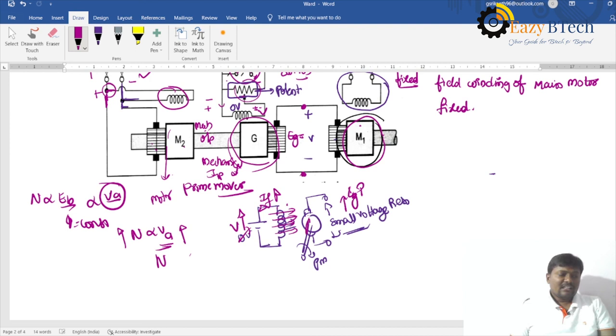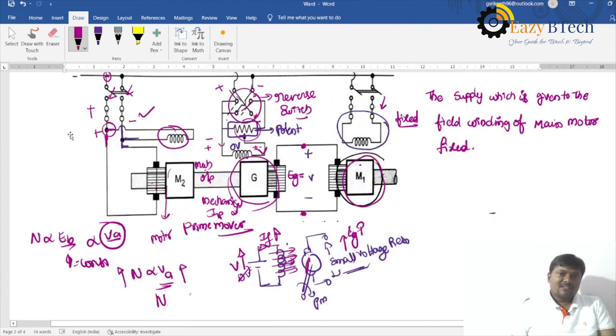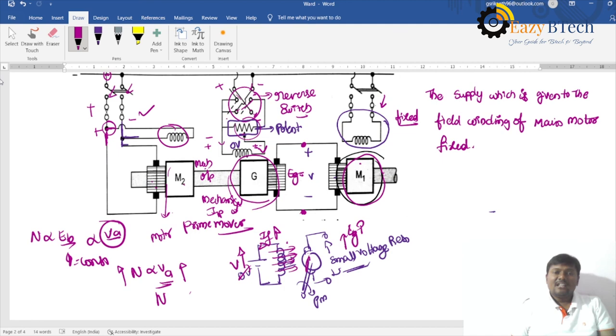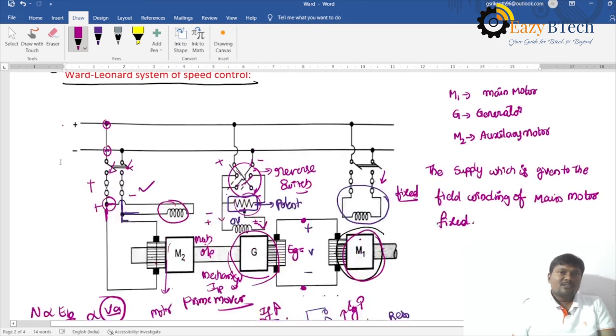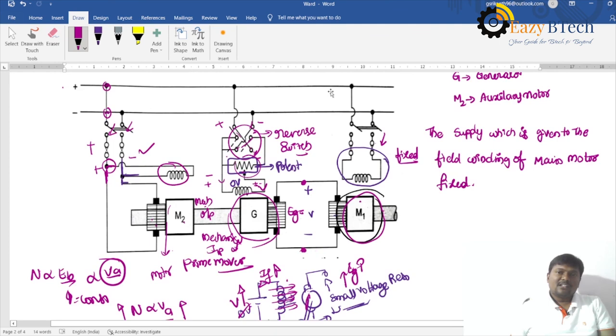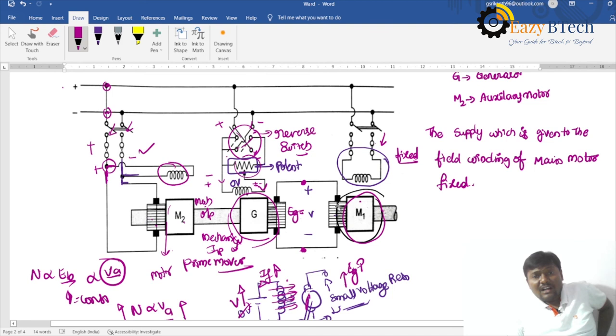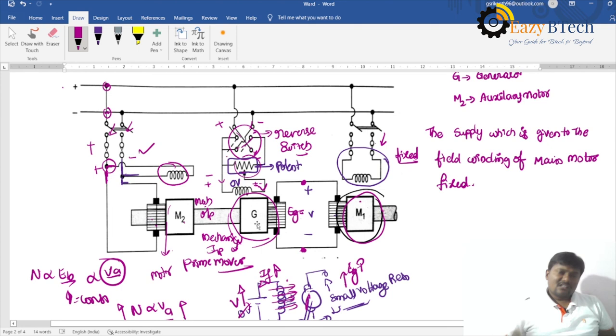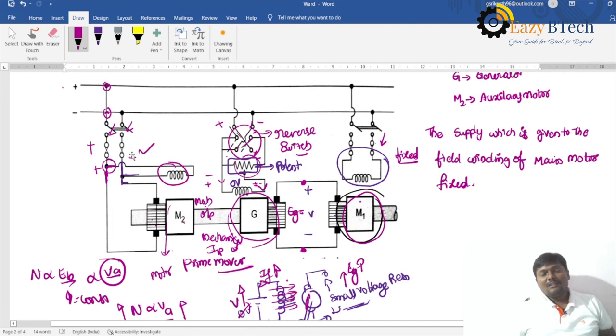This method is used in hoists and elevators. The main disadvantage is that three machines are required, making the cost of this arrangement high. The generator output voltage fed to the motor armature controls the speed; the field winding of the main motor remains at constant supply, and the auxiliary motor drives the generator.